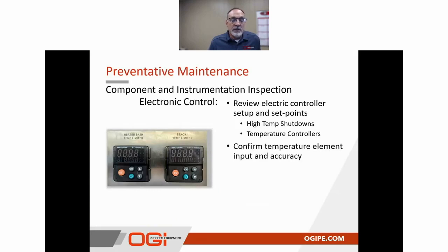In the electronic controls area, we have some electronic temperature controllers and shutdowns. We want to verify that those are actually set up properly, that the temperature elements supplying the indication or measured temperature to these controllers are reading accurately, and finally that the temperature controller set points are correct. And if they're not, then we need to understand, if there's been a change, why. It could be just someone trying to take care of an issue by making an adjustment, versus it being a telltale for another problem if a set point has been changed.